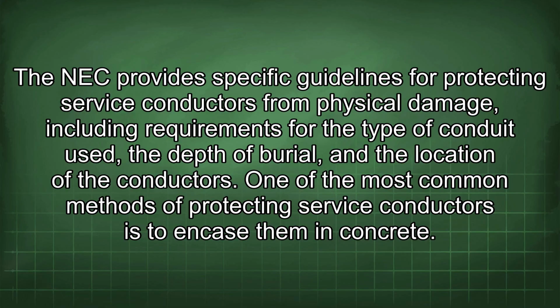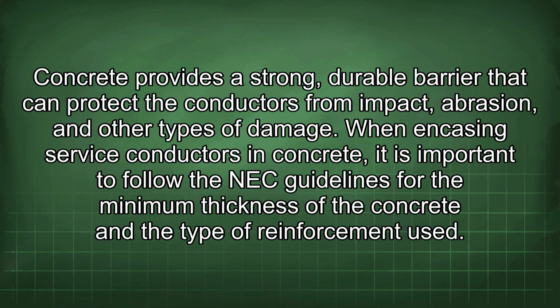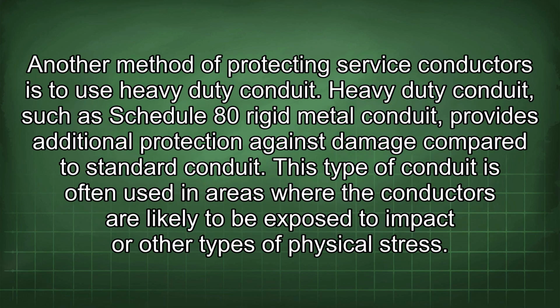One of the most common methods of protecting service conductors is to encase them in concrete. Concrete provides a strong, durable barrier that can protect the conductors from impact, abrasion, and other types of damage. When encasing service conductors in concrete, it is important to follow the NEC guidelines for the minimum thickness of the concrete and the type of reinforcement used. Another method of protecting service conductors is to use heavy-duty conduit. Heavy-duty conduit, such as Schedule 80 rigid metal conduit, provides additional protection against damage compared to standard conduit. This type of conduit is often used in areas where the conductors are likely to be exposed to impact or other types of physical stress.